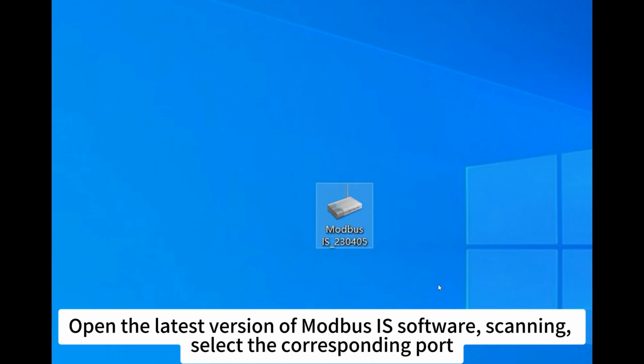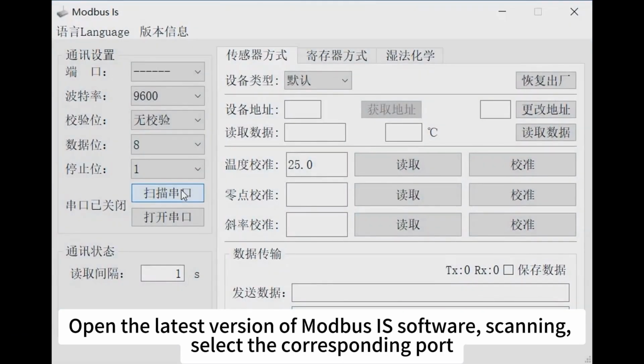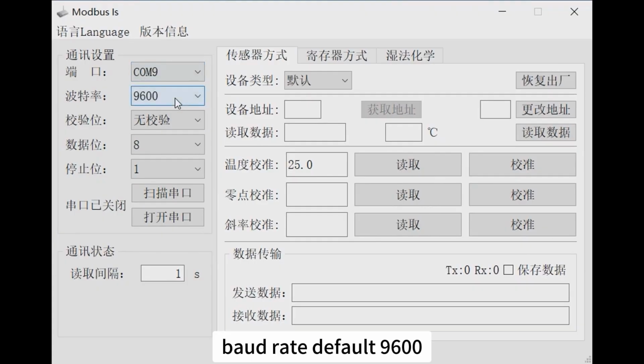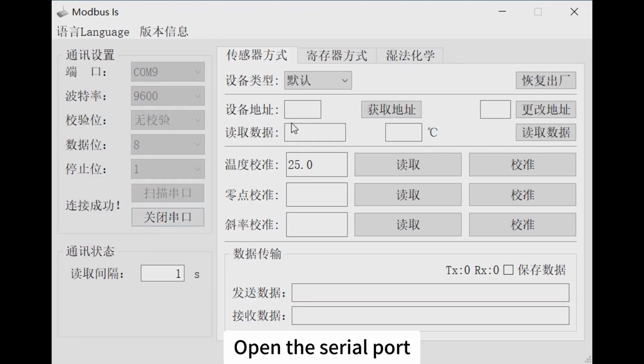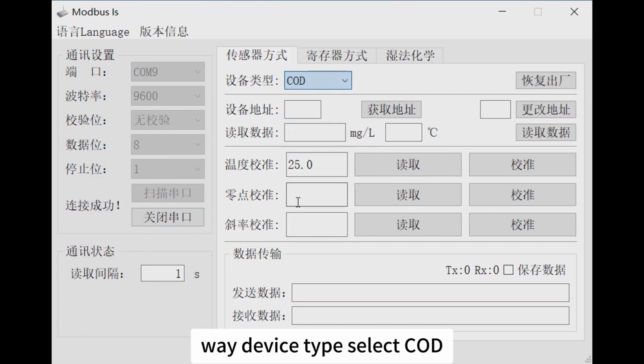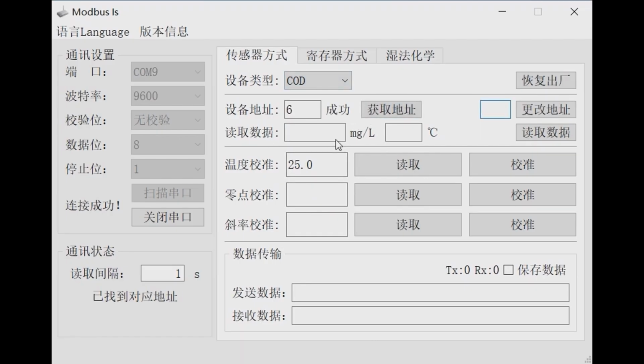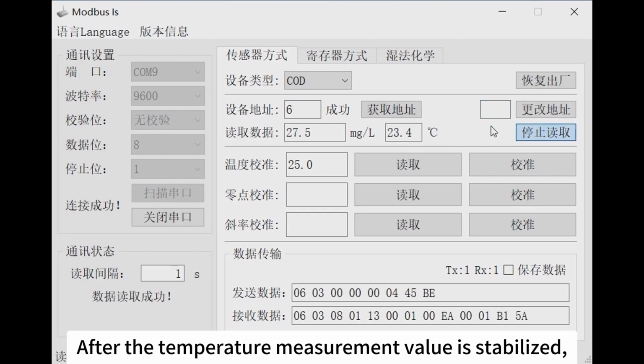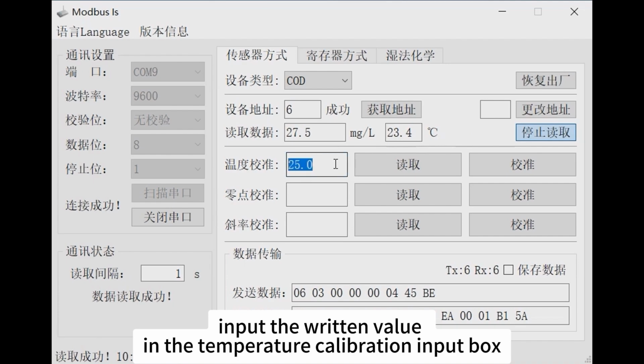Open the latest version of Modbus IS software, scanning, select the corresponding port. Baud rate default 9600. Other keep the default. Open the serial port. Device type select COD. Get the device address. Read the data. After the temperature measurement value is stabilized, input the written value in the temperature calibration input box.